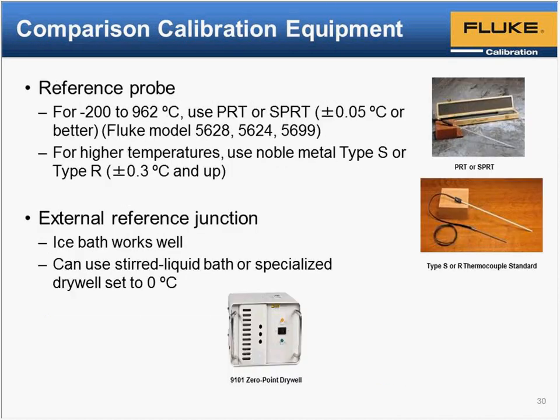Quite commonly, we see people using ref PRTs, platinum resistance thermometers, to provide the reference temperature for thermocouples. For higher temperatures, they also quite often use reference grade type S and type R. And usually they have them calibrated by fixed points so they can get low uncertainties.